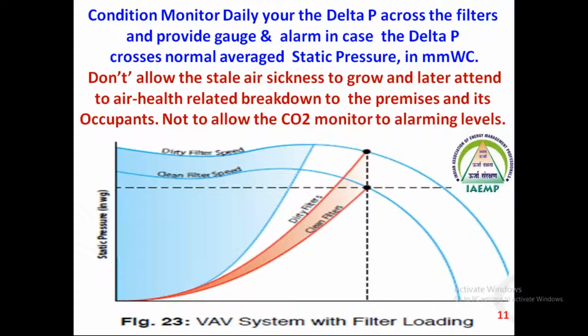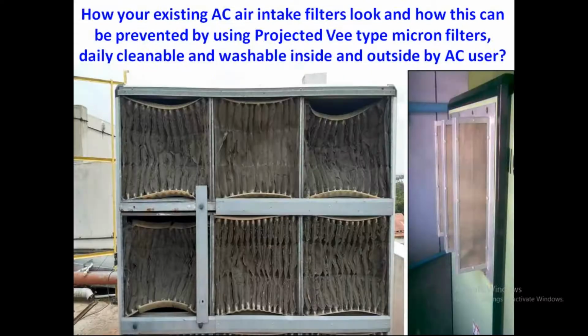If the blower is not pumping air at the required static pressure, straight away staleness or air sickness comes in, and automatically the IAQ of the given department suffers. The CO2 we maintain at around 900 to 1000 ppm definitely becomes a problem and shoots up. So ultimately, the static pressure of a given blower is important in the HVAC segment as well. That is to be monitored.